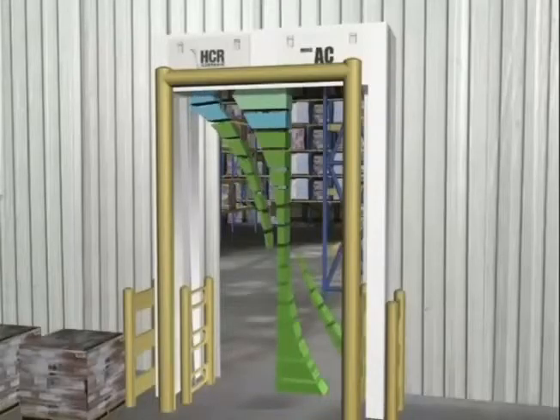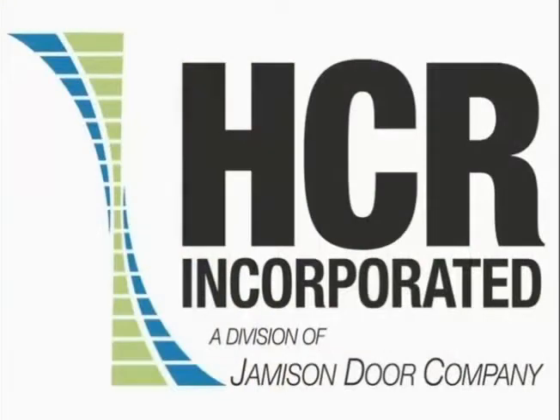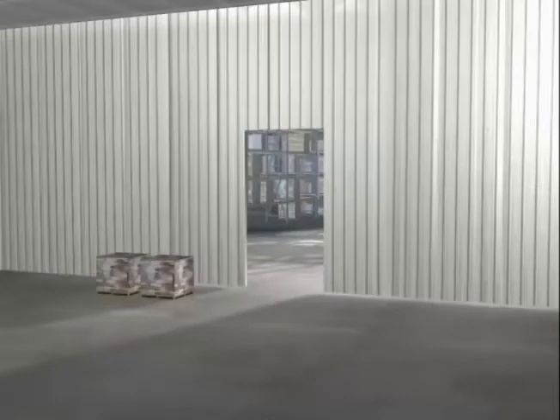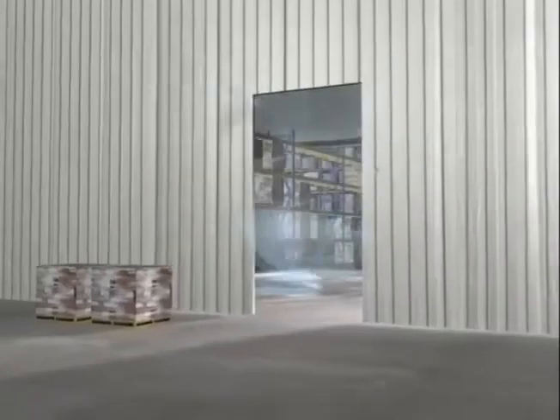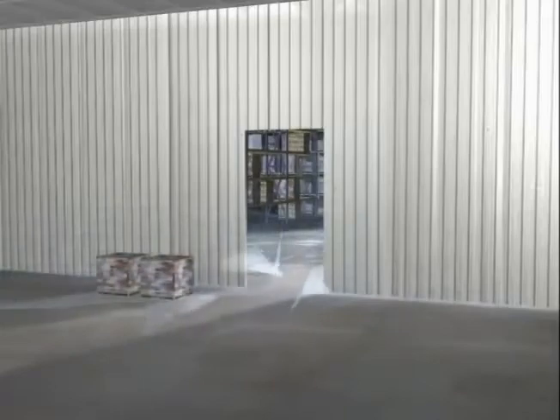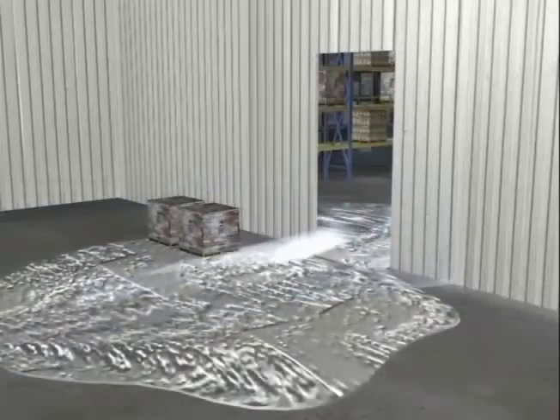According to ASHRAE, the American Society of Heating, Refrigerating, and Air Conditioning Engineers, within seconds after a door is opened, a natural air exchange occurs. In a typical two-way air exchange from a cooler to a freezer or a cooler to a non-refrigerated anteroom, dry cold air from the cold side forces through the doorway at the bottom, while warmer moist air from the warm side pours through the doorway at the top. The escaping cold air flows along the floor where it forms fog and chills the floor below dew point, causing condensation to develop, meaning a slippery, wet, or icy floor.